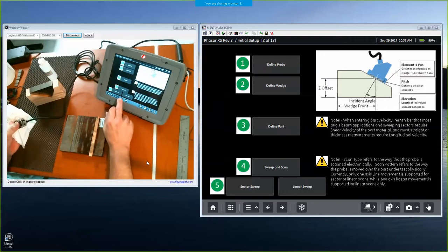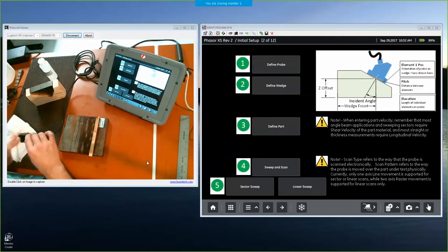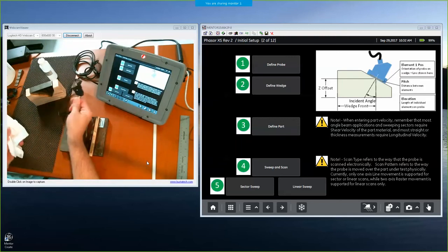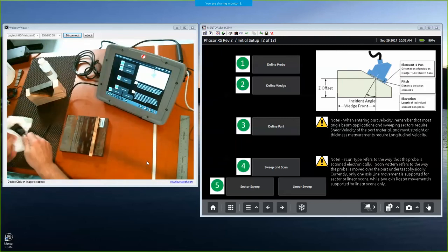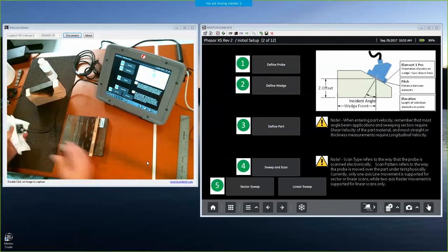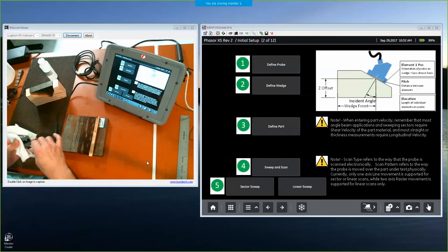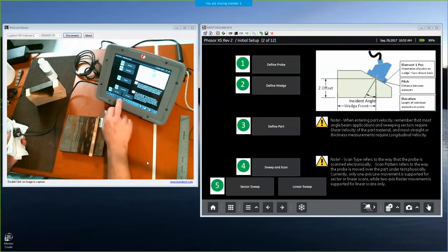So that's all the things that I know from either looking at labels, engraving, either measurements or drawings of my part. A little bit later, we'll look at how the weld overlay is done. There again, you'll need to know from a specifications document that instructed the welder how to make the weld, or just from common practice, you'll know what the shapes are and the angles there.